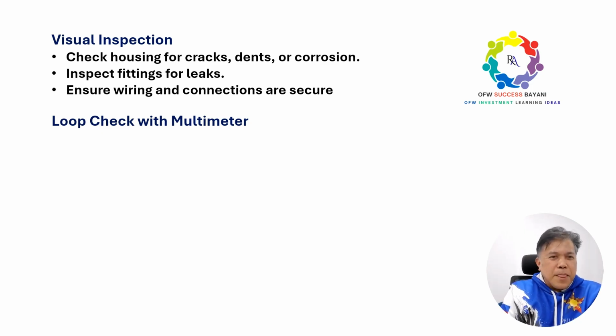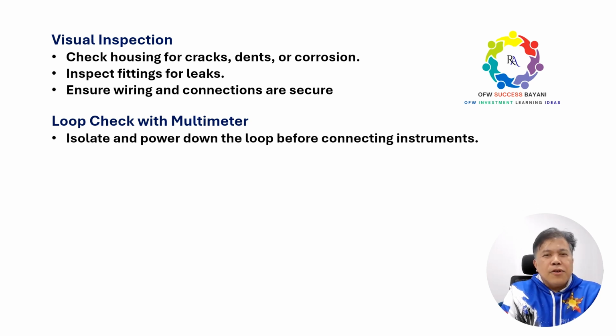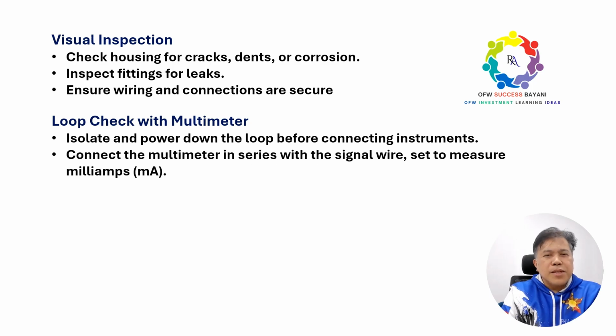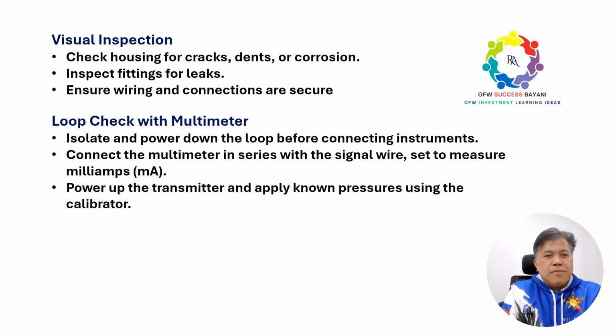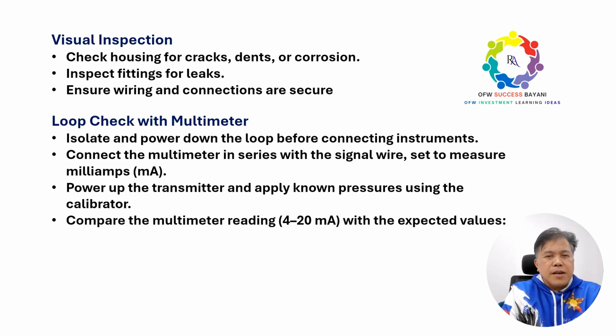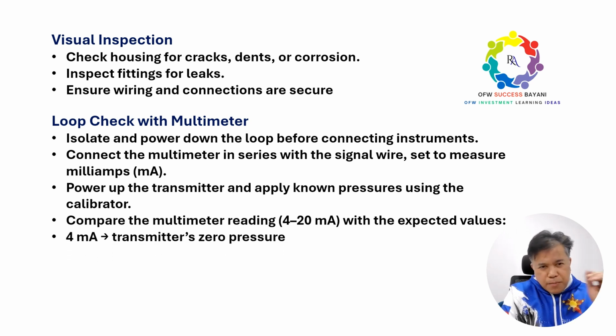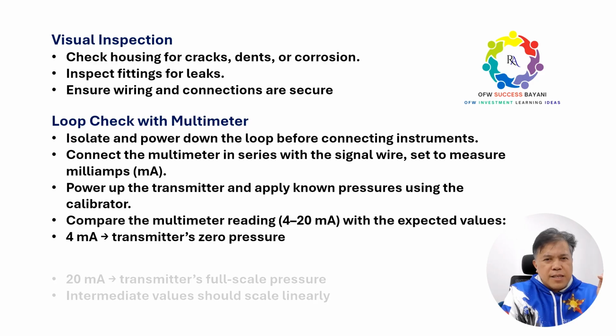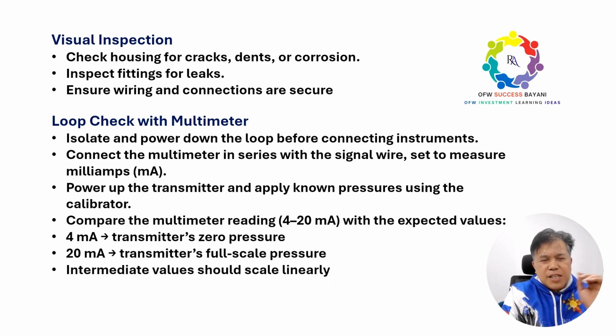So loop check: isolate and power down the loop before connecting instruments, and then connect the multimeter in series with the signal wire, set to measure milliamps. You have two wires. Then power up the transmitter, apply pressure using a calibrator, and compare the multimeter reading, 4 to 20 milliamps, with the expected values. This is the range of our testing, 4 to 20 milliamps, no less, no more. 4 milliamps is transmitter zero pressure. That is zero pressure when you start the 4 milliamps during the testing, and then full scale pressure is 20 milliamps.